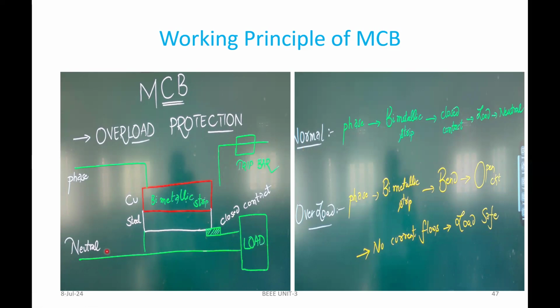For the sake of protection, the overload condition is there now. Under the overload condition, current passes from phase to the bimetallic strip and it can bend it towards the trip circuit. It enlarges like this. That is why we choose a bimetallic strip. When there is an overload, it bends towards this part here, and it can open out.